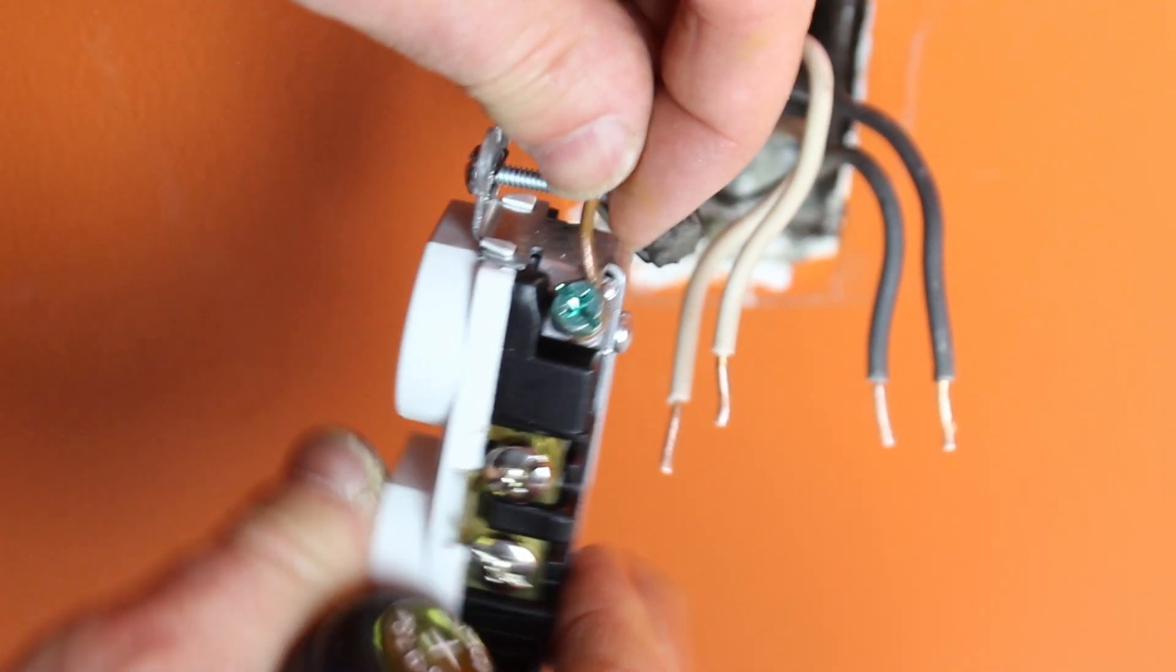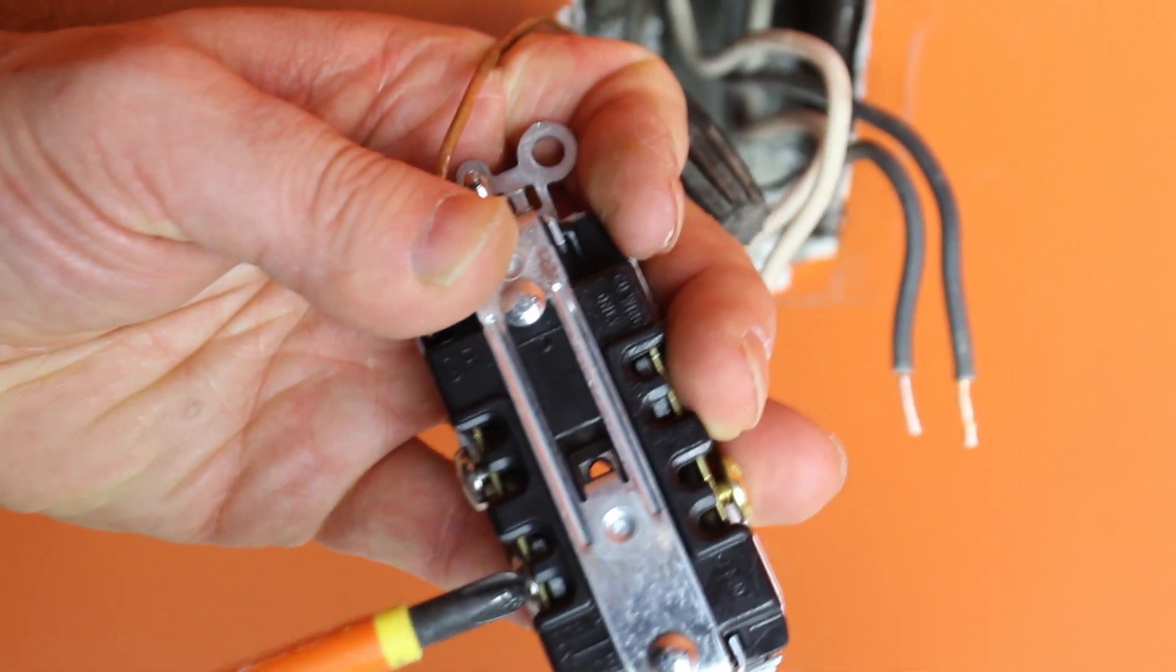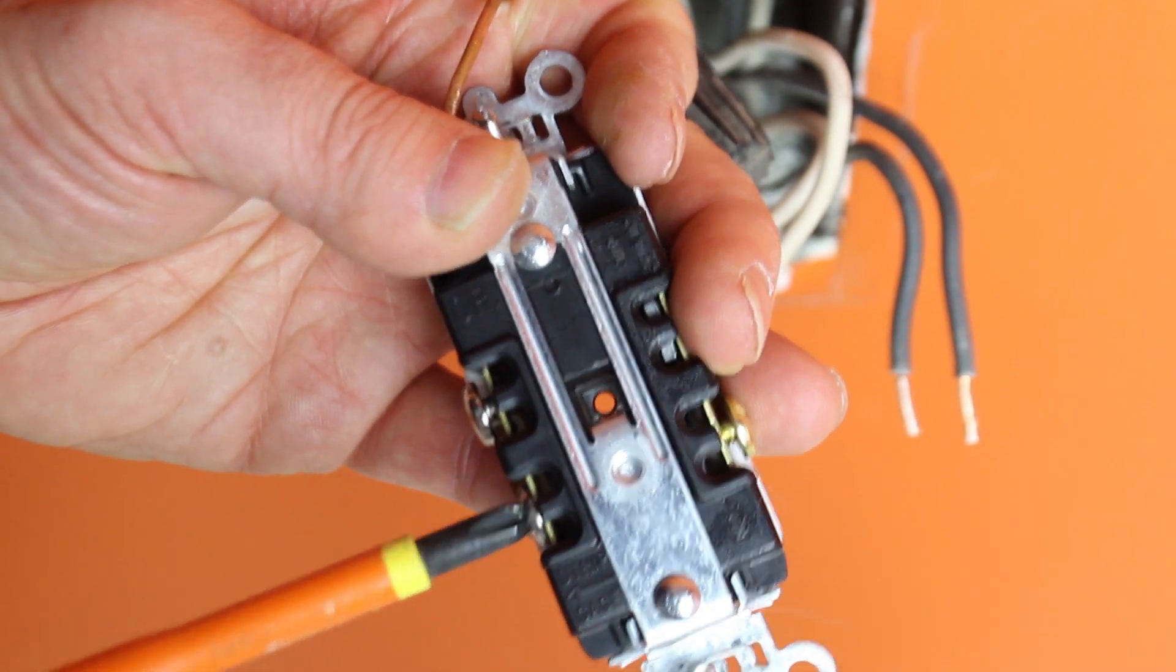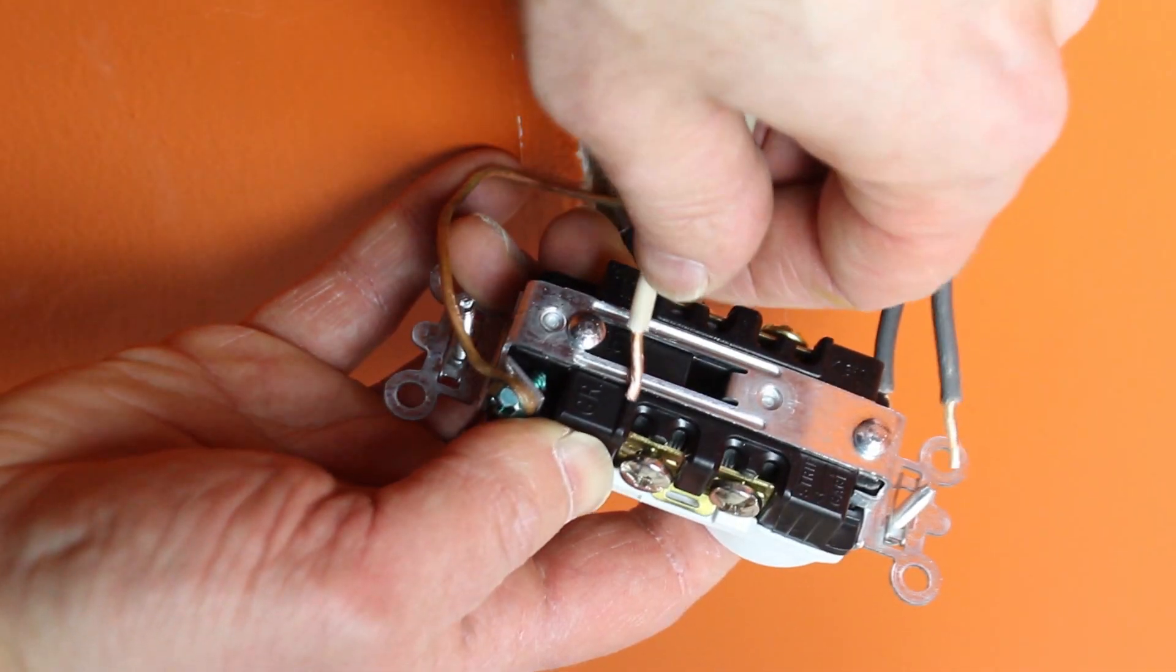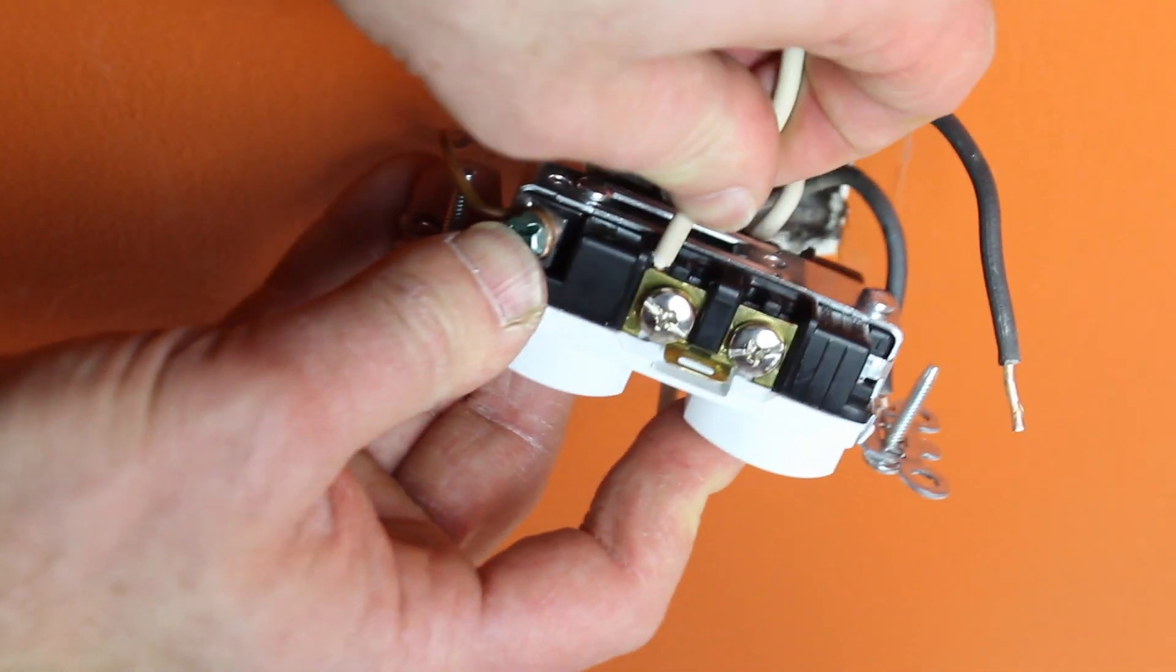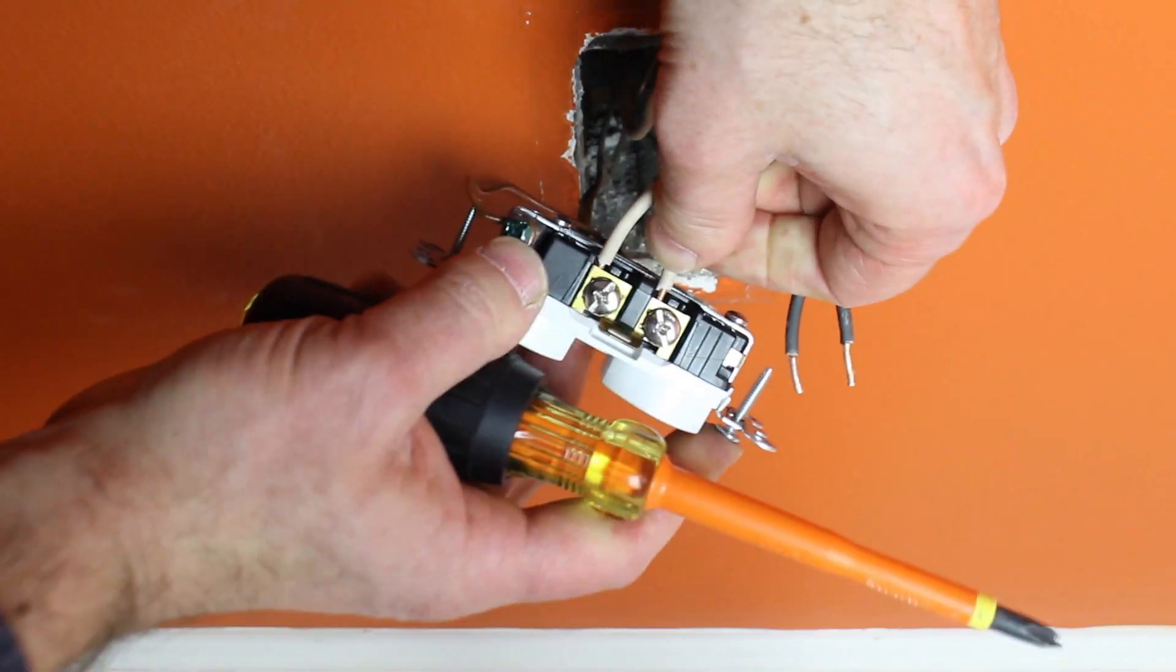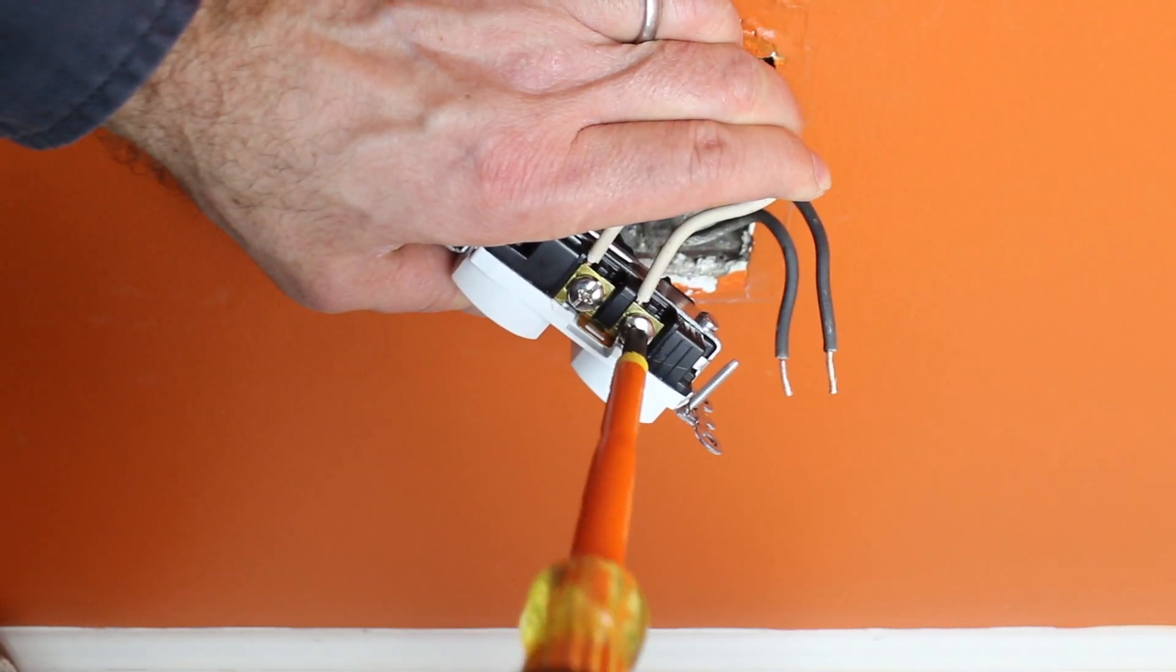The next wires that I like to wire up are the neutral wires. And they go with the silver terminal screws. So loosen the terminal screws by turning them counterclockwise. And in this case, for this Pass & Seymour Outlet, I just pushed the wires into the back—into the slots into the back. And I hold the wires down with one hand while I tighten down the white terminal—excuse me—the silver terminal screws with my screwdriver.